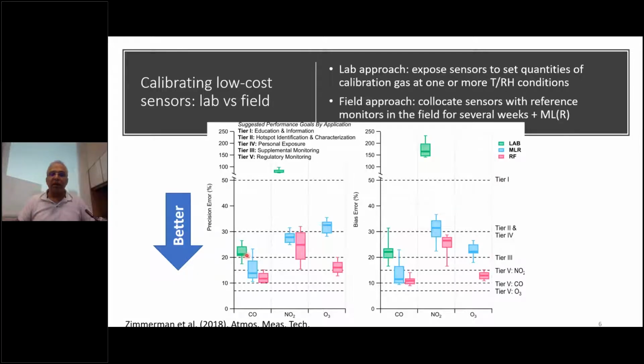So here, the green boxes are the lab-based calibrations. This graph shows the precision error as defined by the US EPA, and this is the bias error. You can see that for NO2, the lab-based calibration has a precision error of greater than 50%, whereas with random forest, you can get that error to closer to 20% or 30%. For ozone, the ambient collocation-based precision error is less than 20%, and the bias is also less than 15%. That's in the magenta. And so with machine learning techniques and with ambient collocations, we can get pretty good data quality out of these low-cost sensors that can be used to supplement a regulatory grade monitoring network.